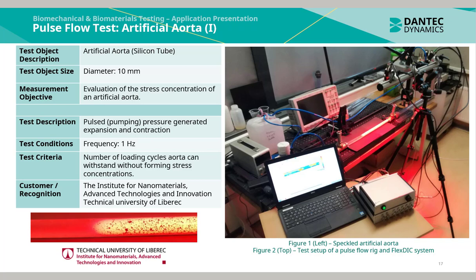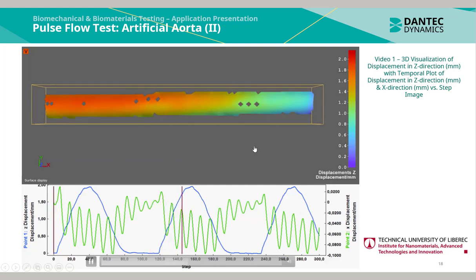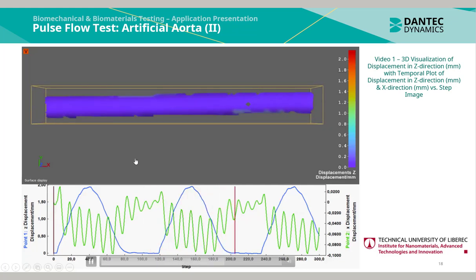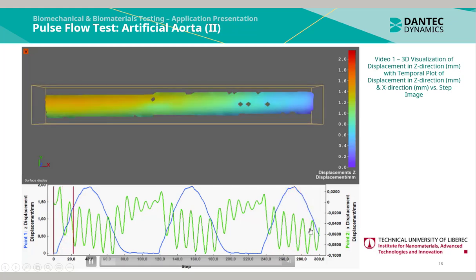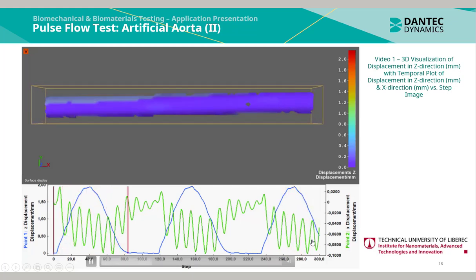The test criteria is to assess the number of loading cycles the artificial aorta can withstand without forming stress concentrations. On the right we see a test setup of the artificial aorta and a FlexDIC system. Here is a video of the 3D visualization of the displacement in the Z direction, with a temporal plot of the displacement in the Z and X directions in millimeters versus the step image.